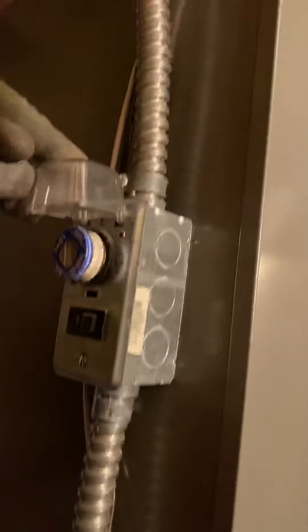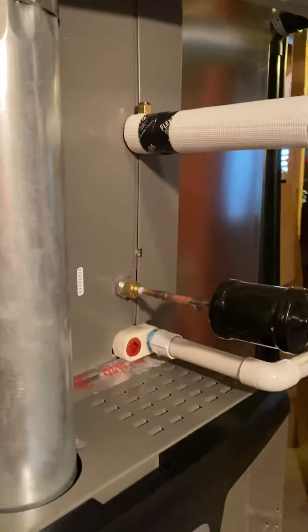Up on the wood and down our electrical — 15 amp, this was already here, we just reused it, didn't have to redo anything as far as that goes. I did redo the plenum, re-tied into their floor drain, combustion air lower and upper for the combustion drain.